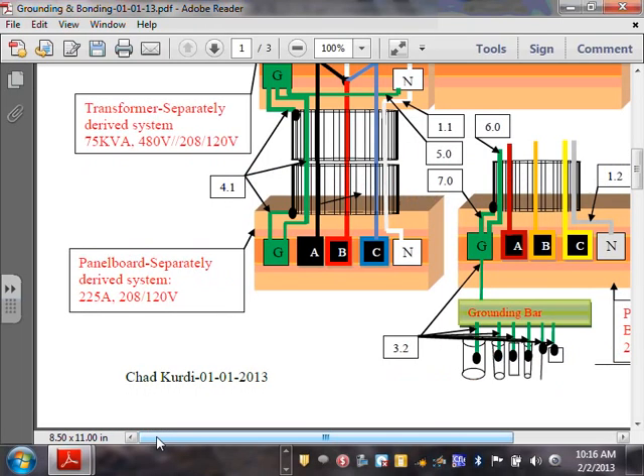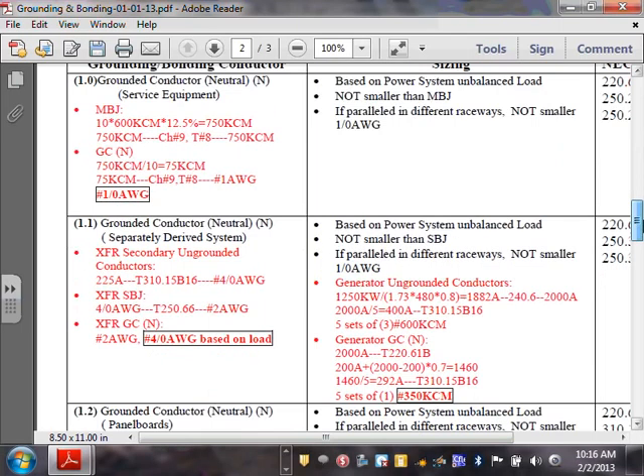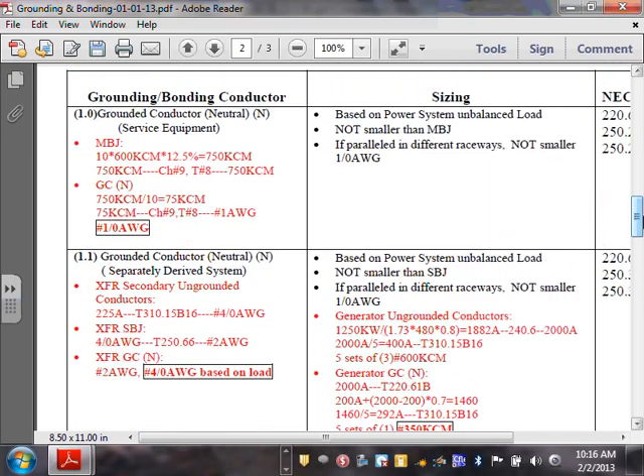Any comment, guys, about sizing this? Sizing it? Okay, so that's my neutral. Why do we care about the neutral when we talk about grounding? Anybody, did you guys ask me, why are you talking about neutral when we talk about grounding, guys? Neutral, the code doesn't call it neutral, it calls it grounded conductor. It is the intentionally grounded conductor. So it has to do with the grounding because it's the intentionally grounded conductor.